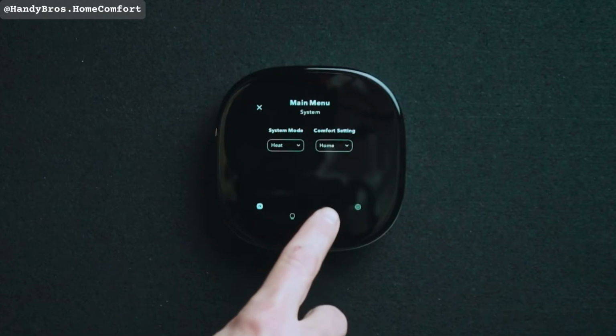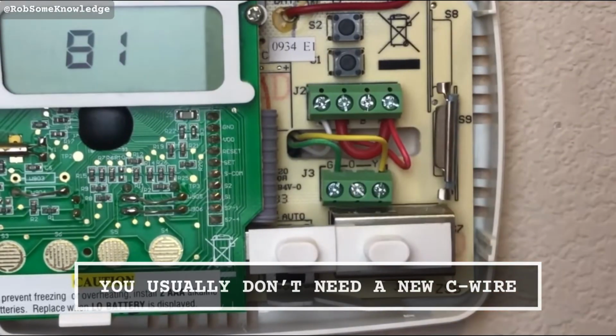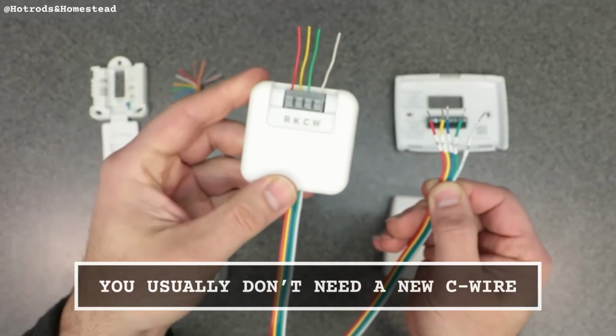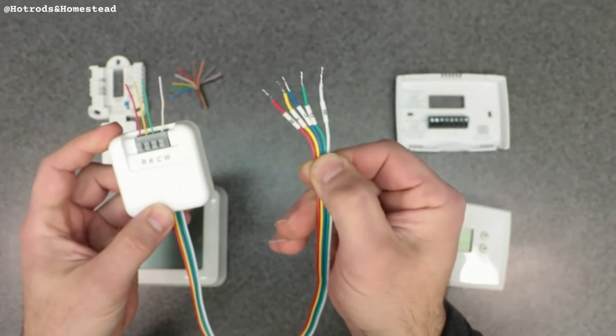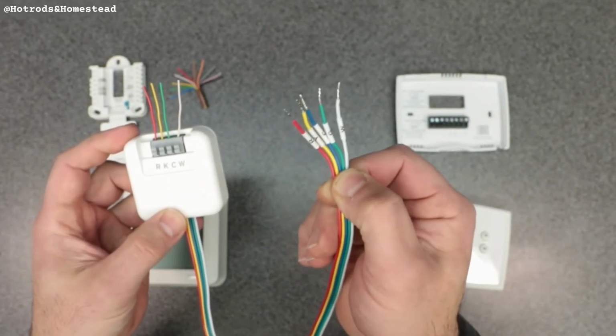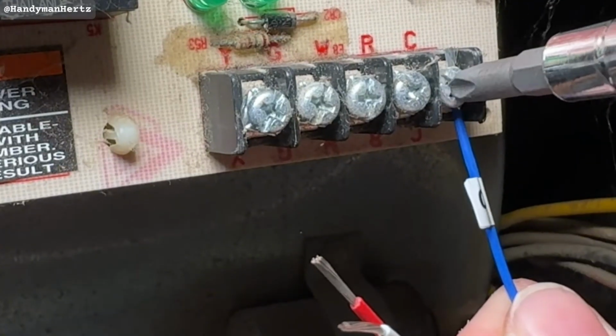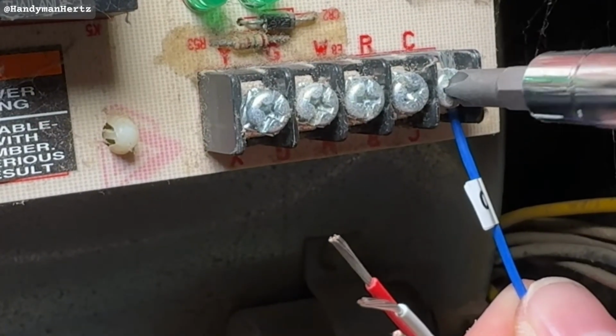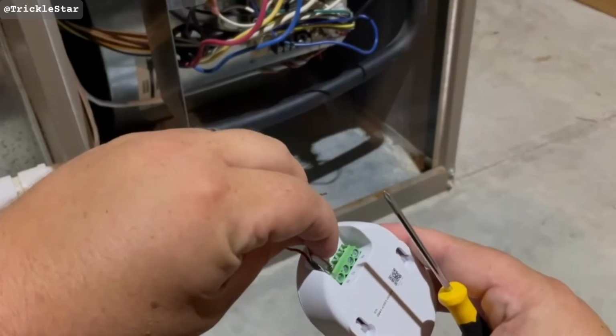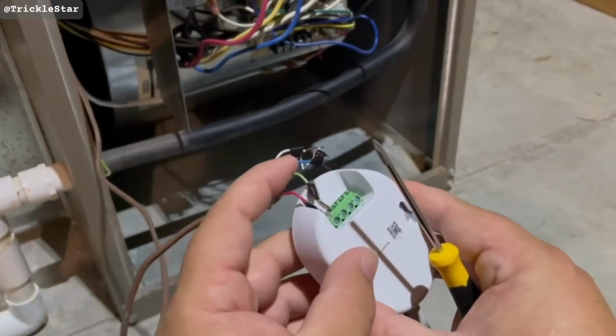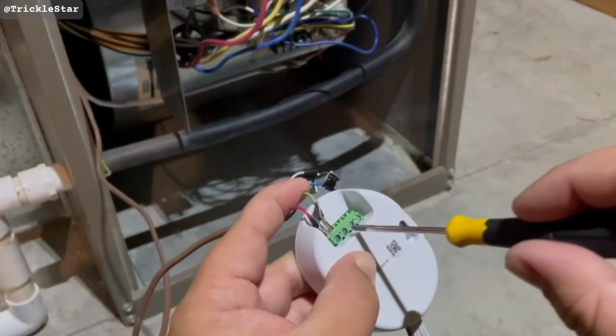Number 25. If your thermostat doesn't have a C-wire and you want a smart thermostat, a $20 C-wire adapter from Venstar or Honeywell works perfectly fine. Contractors regularly quote $200 to $400 to physically run a new C-wire from the air handler to the thermostat. The adapter solves the problem in 15 minutes with no wall fishing.